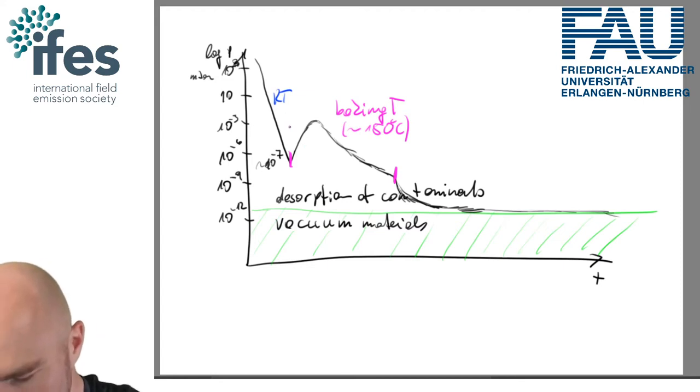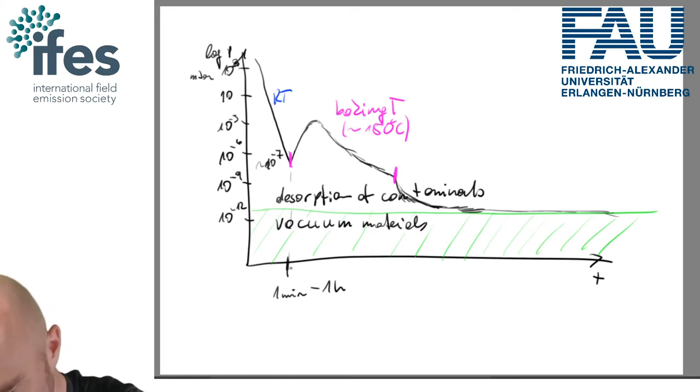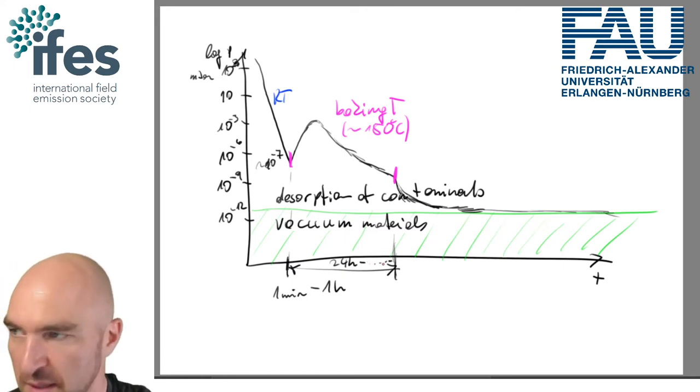And typically, if we go to times, then this would maybe be 1 minute to 1 hour. Then the bakeout period here, until you're done with this, depends on when you actually reach what kind of pressure. You can obviously wait for longer, but this would be something like 24 hours to however long you want. I've done bakes for weeks.